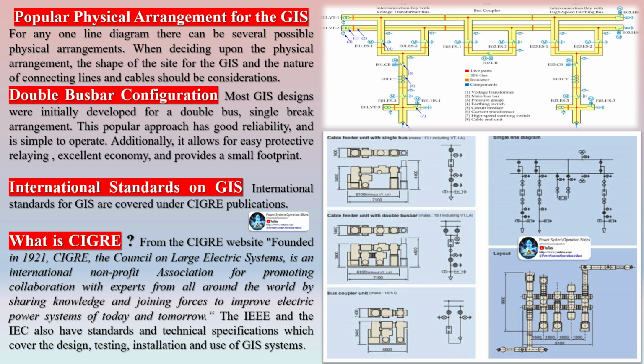For any one-line diagram there can be several possible physical arrangements. When deciding upon the physical arrangement, the shape of the site for the GIS and the nature of connecting lines and cables should be considerations. Most GIS designs were initially developed for a double-bus, single-break arrangement. This popular approach has good reliability, and is simple to operate. Additionally, it allows for easy protective relaying, excellent economy, and provides a small footprint.